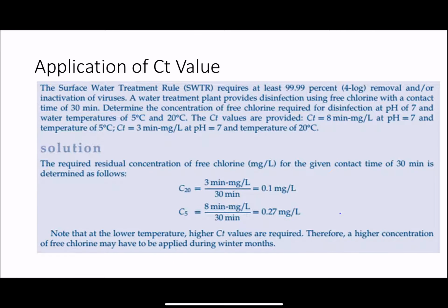Let's look at this application of CT. Surface water treatment requires at least 99.99% inactivation. 99.99% inactivation means 1, 2, 3, 4; we call it 4 log removal. So 99.9% is 3 log removal. This is one abbreviation we use a lot. So 4 log means 99.99%.